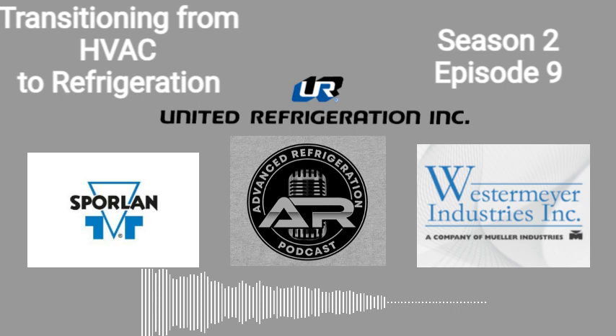Same thing with rack stuff, which I know, Kevin, you and I have talked about a bunch. Medium temp condenser TD is anywhere from 12 to 18 degrees. Low temp rack, you're talking anywhere from 8 to 12. So remembering those rules of thumb will get you in the ballpark a lot if you don't have the exact spec of what it should be. Yeah, exactly. I have to credit my brother, Ryan, for a large portion of my thought process going into calls.